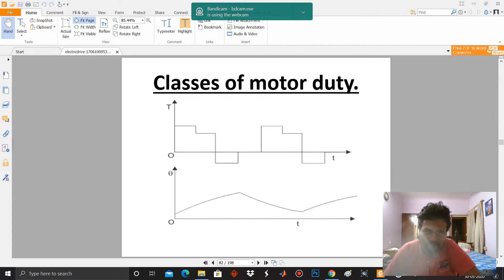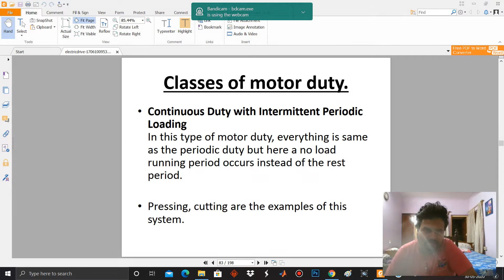The next comes continuous duty with intermittent periodic loading. In this type of motor duty, everything is the same as the periodic duty, but a no load running period occurs instead of the rest period. Pressing and cutting are examples of this system. So let us see how the torque profile looks like.